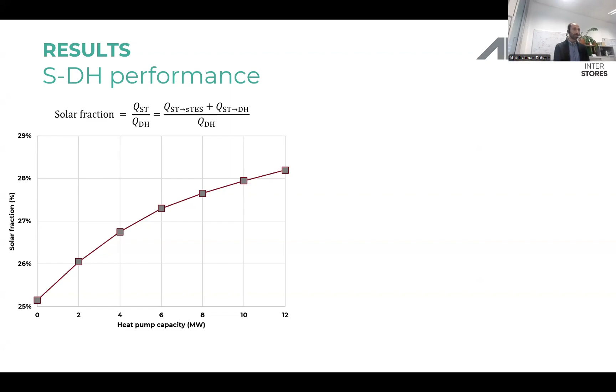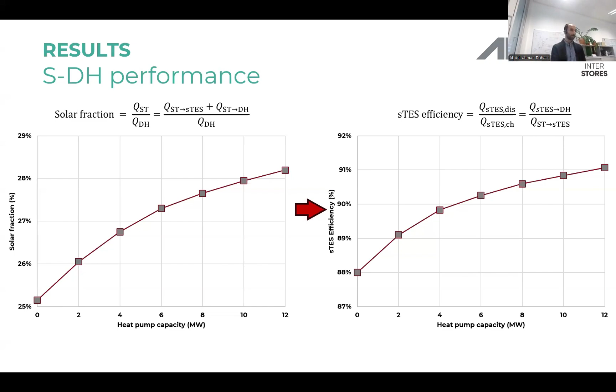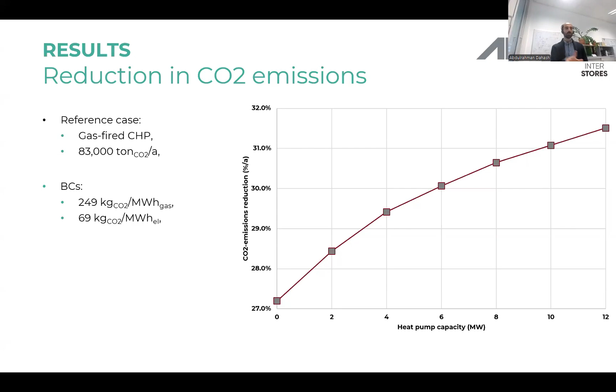The main reason behind that one, because a heat pump coupled to the seasonal thermal energy storage would allow the thermal energy storage to be deeply discharged from the set point of around 50 degrees Celsius down to a minimum of 20 degrees Celsius, which means extra storage capacity, and simultaneously that means also lower losses, better efficiency, and more accommodation of solar fraction. Now, if we consider as well the avoidable CO2 emissions or the reduction on annual basis compared to our reference case, we can boost it up to 31% if we install a seasonal thermal energy storage with a heat pump that has a capacity of around 12 megawatt.